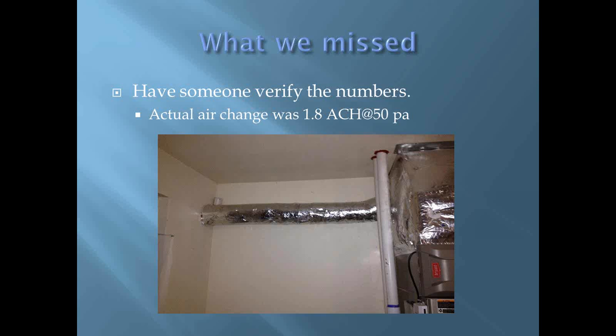In my house, this really turned out to be the solution because the crawl space ventilator pulled too much air out. And so I relayed it to the furnace. The furnace is set to recirculate 35% of the time. Furnace comes on, crawl space ventilator comes on, keep the pressure negative. Transfer grill in the house, fresh air coming through the furnace being distributed through the house. It works so well that I have less than 1 degree temperature variance in any room, any time of the year. That's how good it works.